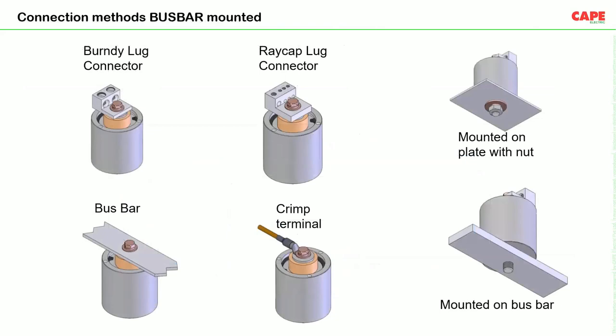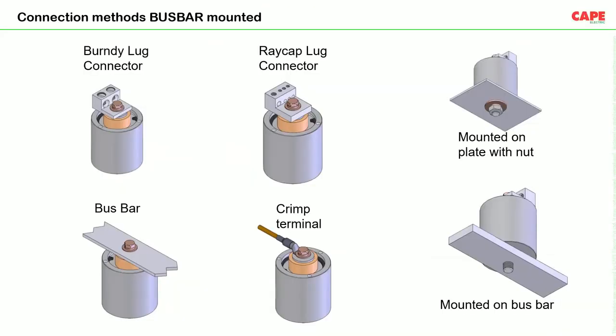So this is how a normal Strikesorb can be connected. Various lugs can be used. It can be mounted on a plate and then connected with a nut. It can be mounted on a busbar. It can be used through a crimp terminal. A busbar can be connected on the screw. These are the various connections for Strikesorb. So this was the general technical description about the SPDs.